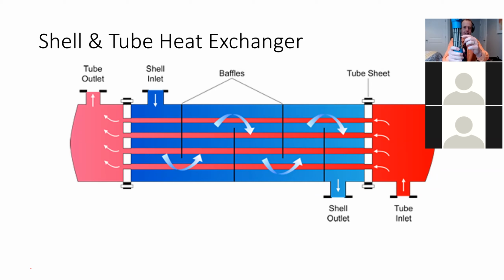These things right here that you can kind of see are cutting off part of the tubes, maybe about 2/3 of the way through the shell. Those are called baffles. And we do that to make the flow go back and forth and increase H, make it more turbulent. That does increase pressure drop, but you want that, so there's a balance. If I put these really close, then it's a really high pressure drop. If I put them further away, it's a lower pressure drop, but I have less heat transfer. So there's a balance that we make here. And you can kind of see that on this diagram right here.